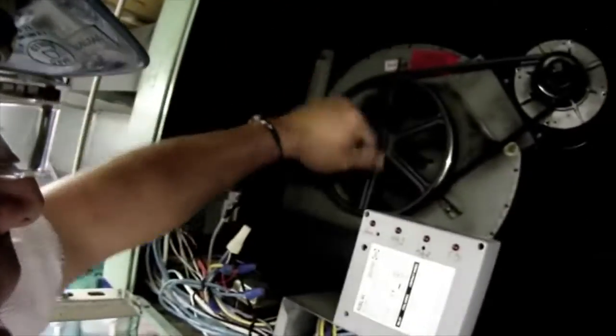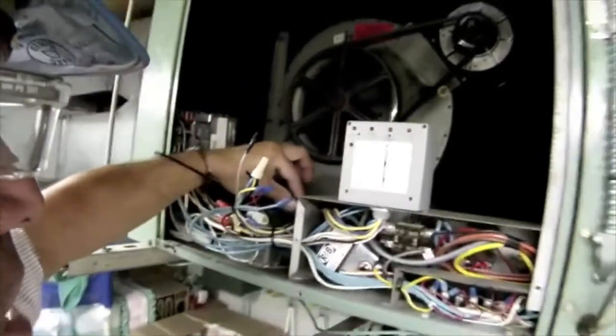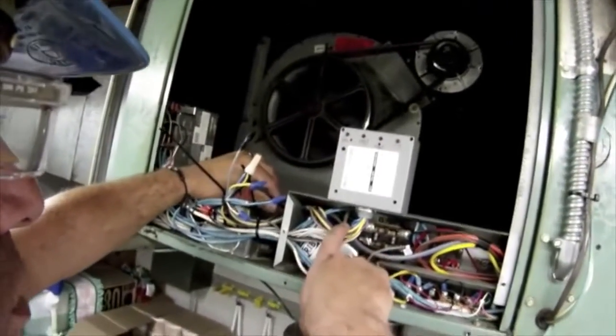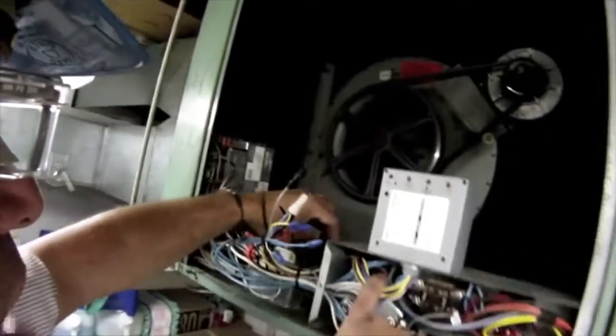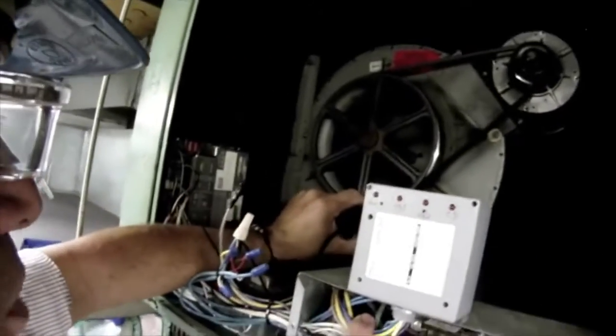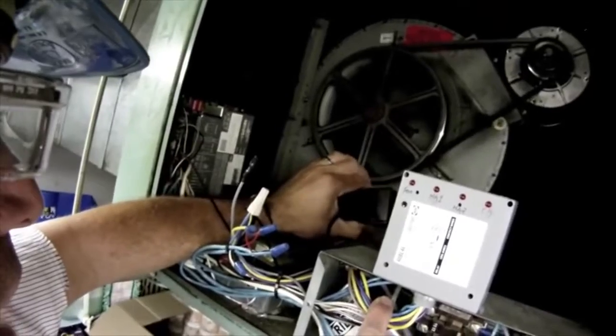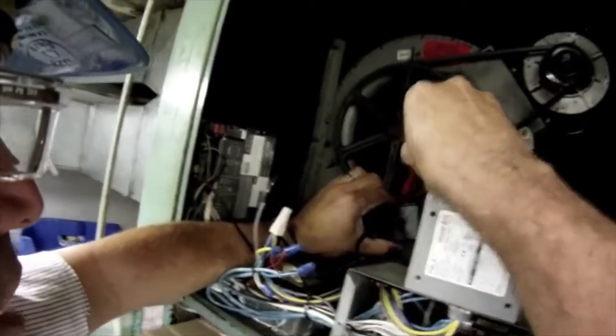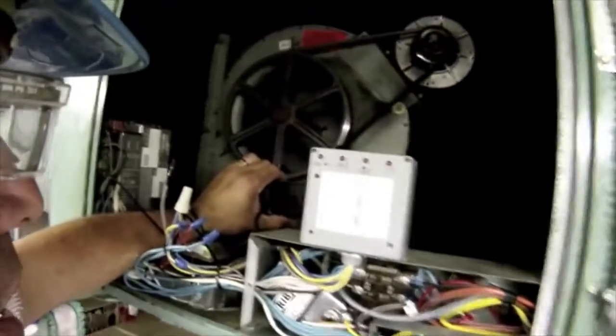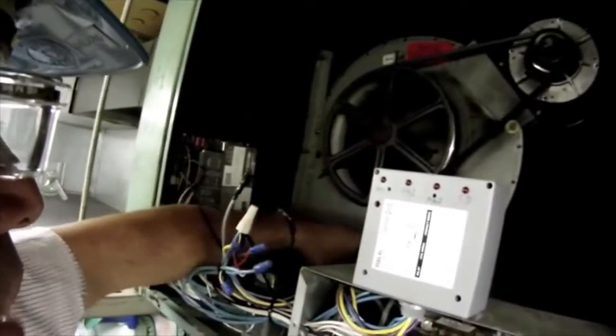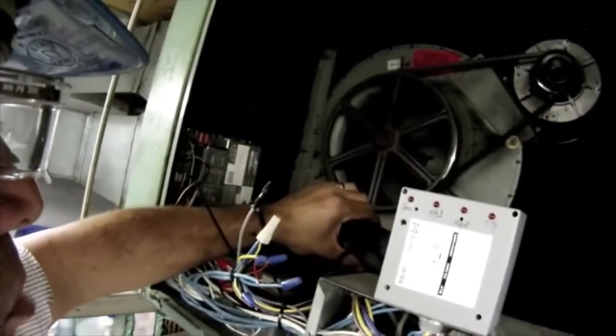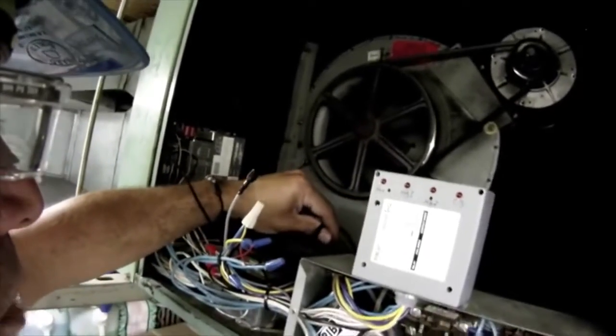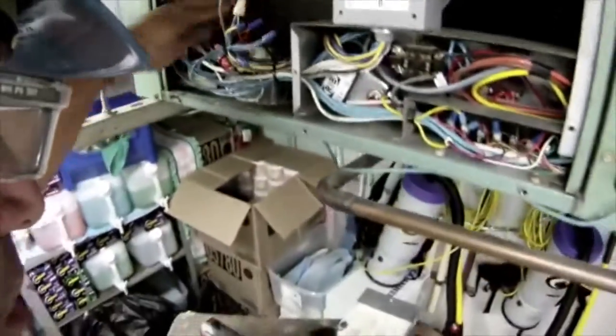My fan motor, I have right here a lead off the load side of the contactor, the black lead, that's the common lead on the fan motor, and I have what's called a tattletale on that, so that this communicates with the digital command system, and then on my laptop I can take a look and verify whether the fan motor's running or not. But this is the common lead, and this is where I'm going to take my amp draw today on my fan motor. So let's get my tool.